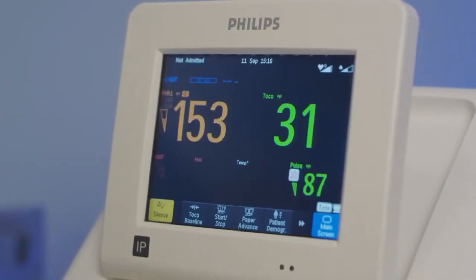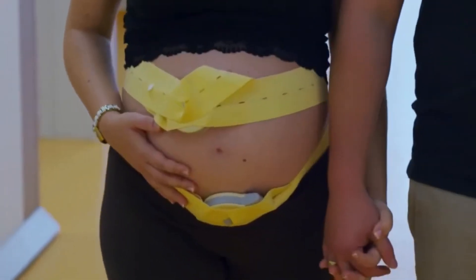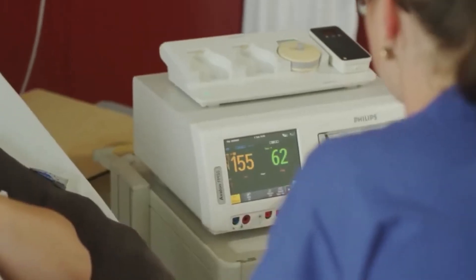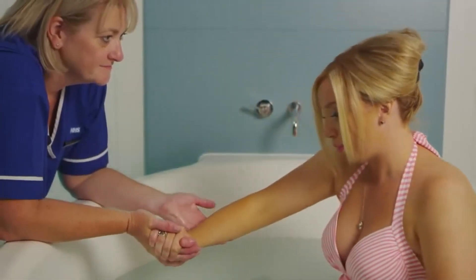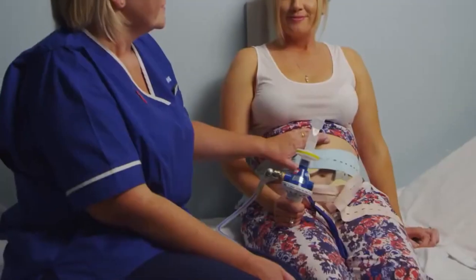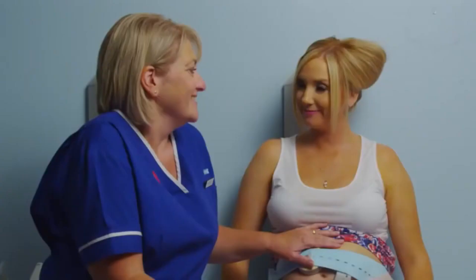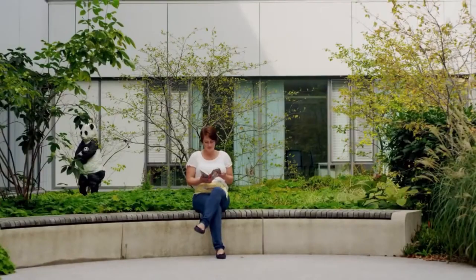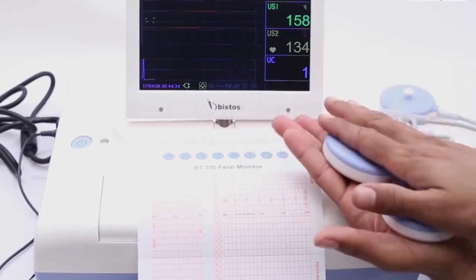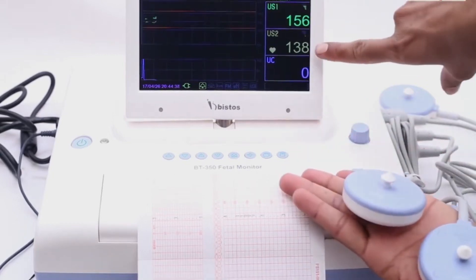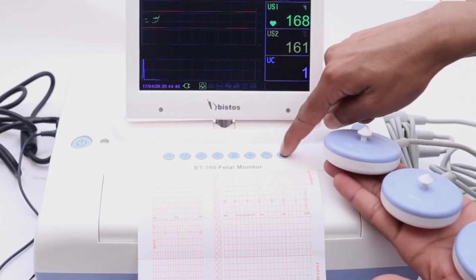The fetal heart rate and activity of the uterine muscle are detected by two transducers placed on the mother's abdomen — one above the fetal heart to monitor heart rate and the other at the fundus of the uterus to measure frequency of contractions. Doppler ultrasound provides this information, recorded on a paper strip known as a cardiotocograph. External tocometry is useful in showing the beginning and end of contractions as well as frequency, but not the strength of contractions. Absolute pressure readings on an external tocometer depend on position and are not sensitive in people who are obese. When information on the strength or precise timing of contractions is needed, an internal tocometer is more appropriate.